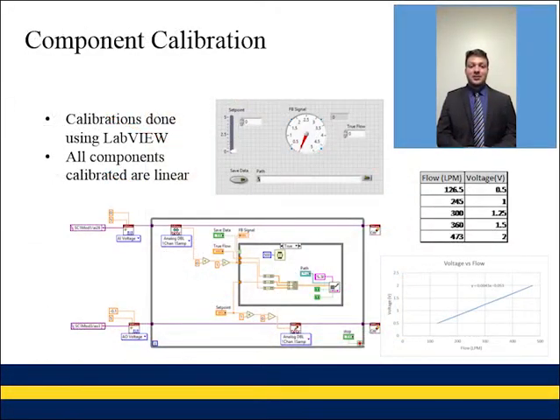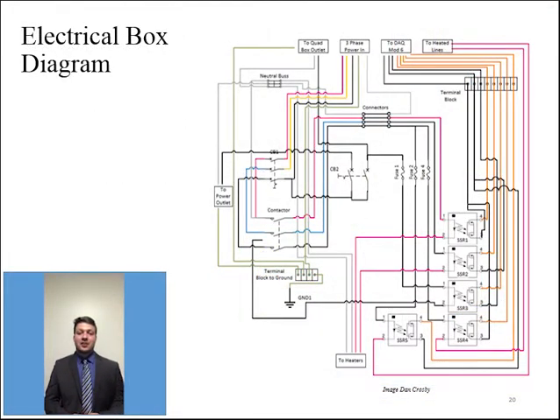On the test stand, there were a few components that needed to be calibrated, such as pressure transducers and flow controllers. We were able to calibrate these using LabVIEW, and we would set up a VI for each component. For the flow controllers, we would incrementally increase the voltage, and we would compare that to a known reading of flow through the flow controller. For the pressure transducers, we incrementally increased the pressure, and were able to compare that to the voltage reading we were getting from the transducers. Thankfully for us, the calibration for every component on the stand was linear, so it was very easy to calibrate. Also for the test stand, we had to set up the electrical box.